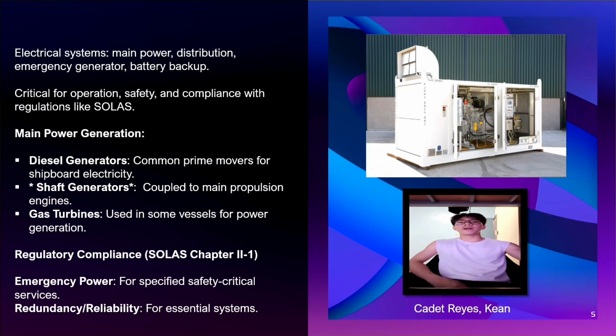Finally, we have the battery. Batteries act as the last line of defense. They are always on standby and provide power instantly when both the main power and the emergency generator are unavailable, or before the emergency generator starts up. Battery backups are usually connected to very critical systems such as alarms, control panels, and communication devices. Their supply time is limited, maybe minutes to an hour, but it's enough to keep essential systems alive until the emergency generator takes over. So, to sum it all up, the main power runs the normal operation. The distribution system delivers it safely. The emergency generator serves as backup during blackouts.